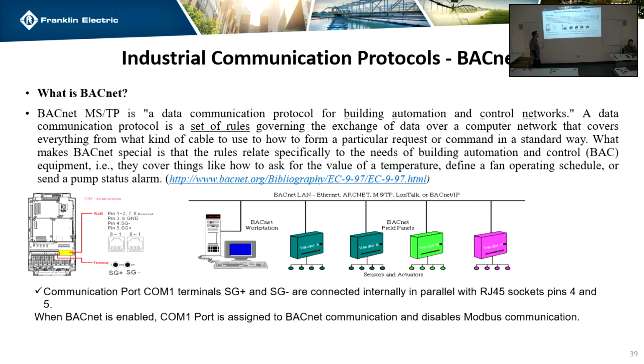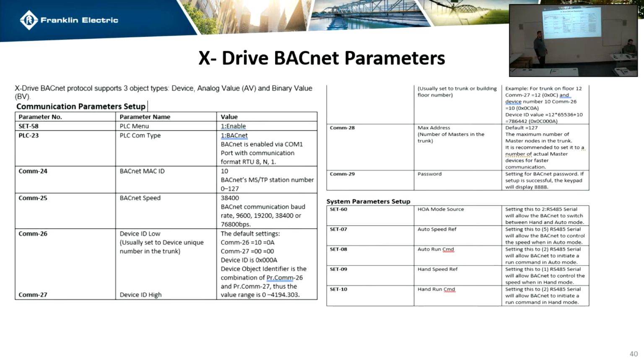Just like Modbus, I am not a BACnet expert. I do have BACnet on my computer, so I will be able to hook it up, look for things, and see if something's not working the way it's supposed to. But for the most part, the BACnet guys are going to need to know how to troubleshoot BACnet. Almost always it comes down to wiring, putting too many things on a trunk, having termination switches on halfway through the line, things like that. Are there dip switches for the MAC address, or do you have to set it up in the... It's all inside the drive. All right. Yep.